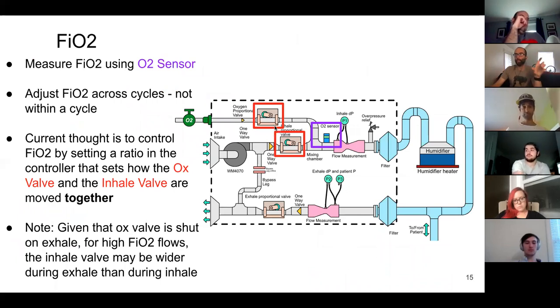But I just want to emphasize the point that we're not controlling O2 rate during the breath. So we're not going to say, hey, not only is pressure low, but the O2 concentration is also low, right? We're going to try and simplify the system dynamics, and do this as an adaptive control over multiple breaths. So it might take 3 or 4 breaths for that proportionality rate to converge on a value that hits the FiO2 target. So if we're trying to get to 60% FiO2, we're going to have a guess value of how much both of these valves need to swing open to get to 50-50. And then we're going to average out the O2 over the breath and say, hey, FiO2 was targeting 60, but it came out to 55%.